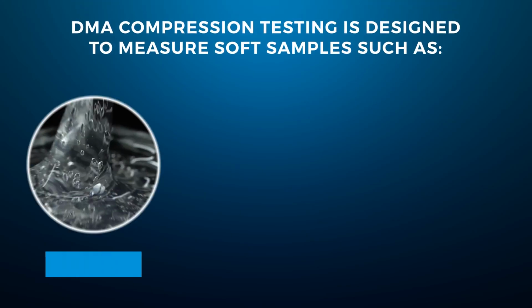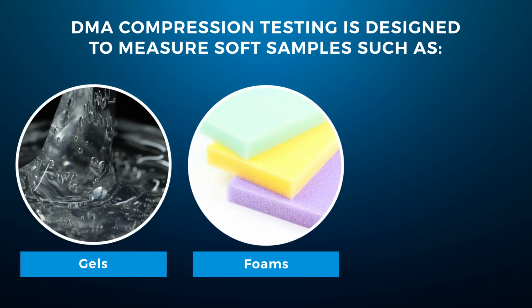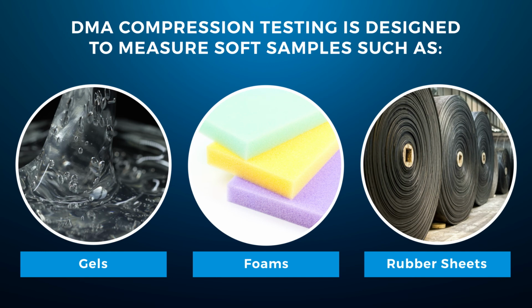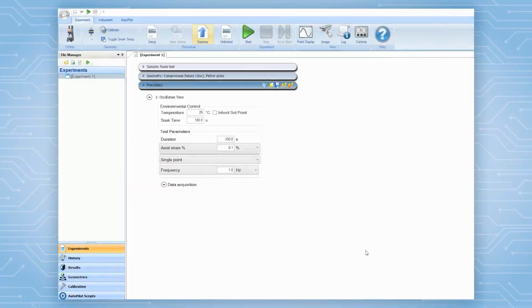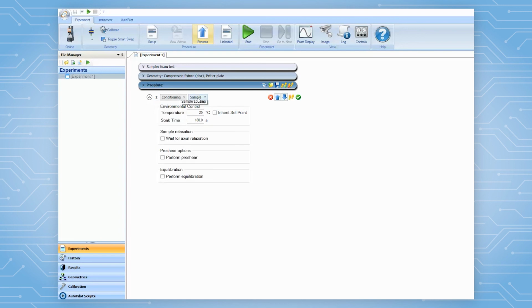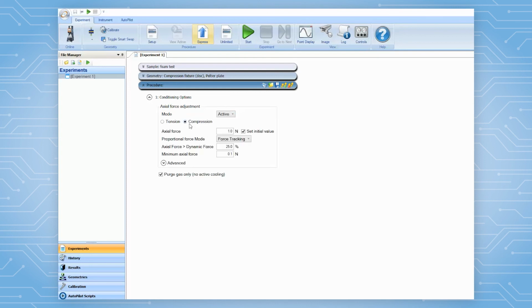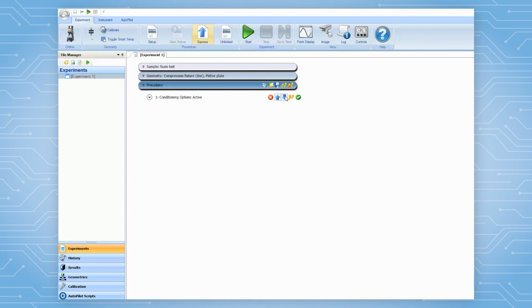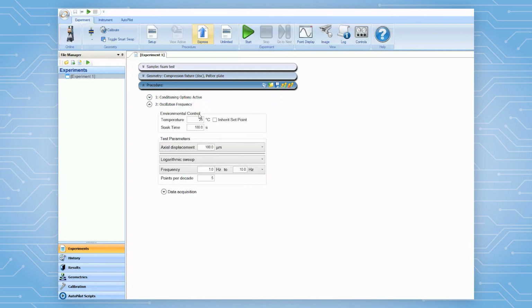Please note, DMA compression testing is designed to measure soft materials such as gels, foams, or rubber sheets above their glass transition temperature. For example, setting up a compression frequency sweep test on a foam sample will include 2 steps. In the first conditioning step, the operator needs to set up the appropriate initial preload force and the force tracking conditions based on sample's stiffness. Then in the second step, set up the specific frequency sweep test parameters.